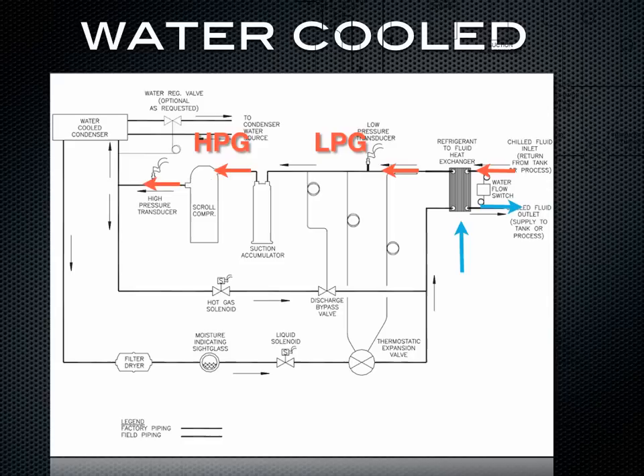That high-pressure gas is going to leave the compressor and go to the water-cooled condensers, and that heat will be rejected to a cooling tower, building water, or geothermal. Now how that works is the second law of thermodynamics. The temperature of that high-pressure gas could be 210 degrees. The cooling tower or building water could be around 85, 105, or even 115 degrees. The second law of thermodynamics will come into play because that cooling tower water is a lot colder than your high-pressure gas, so the heat will go towards that.